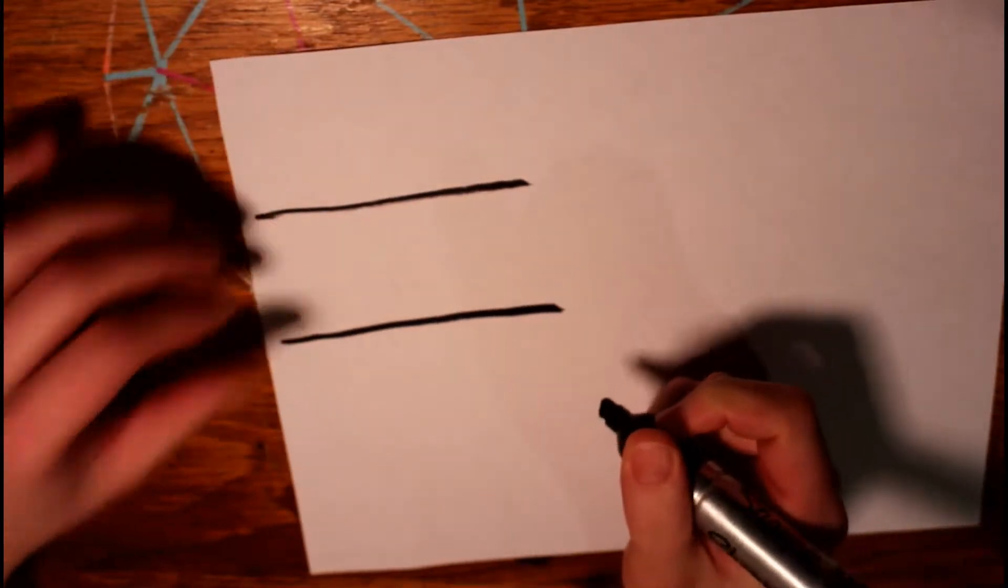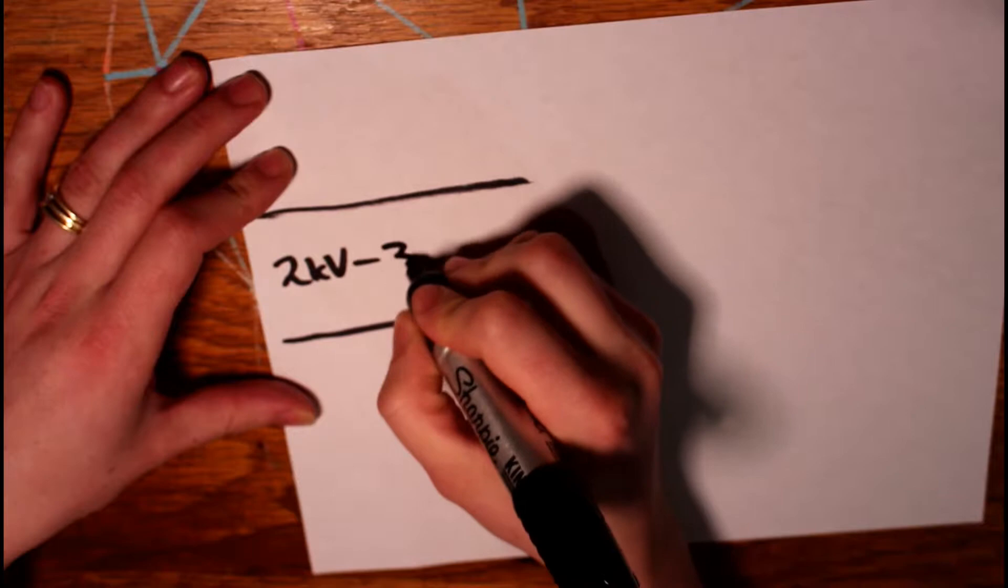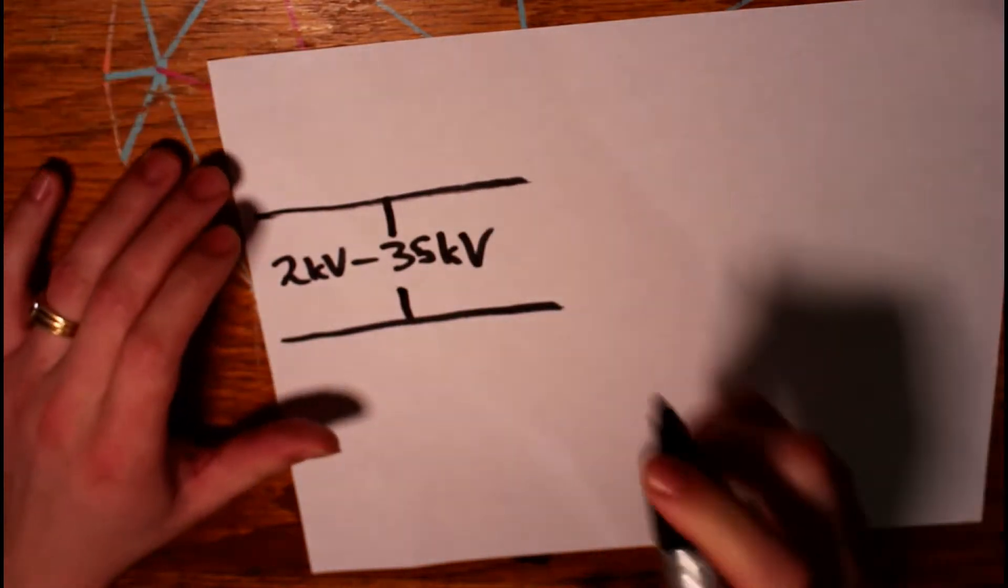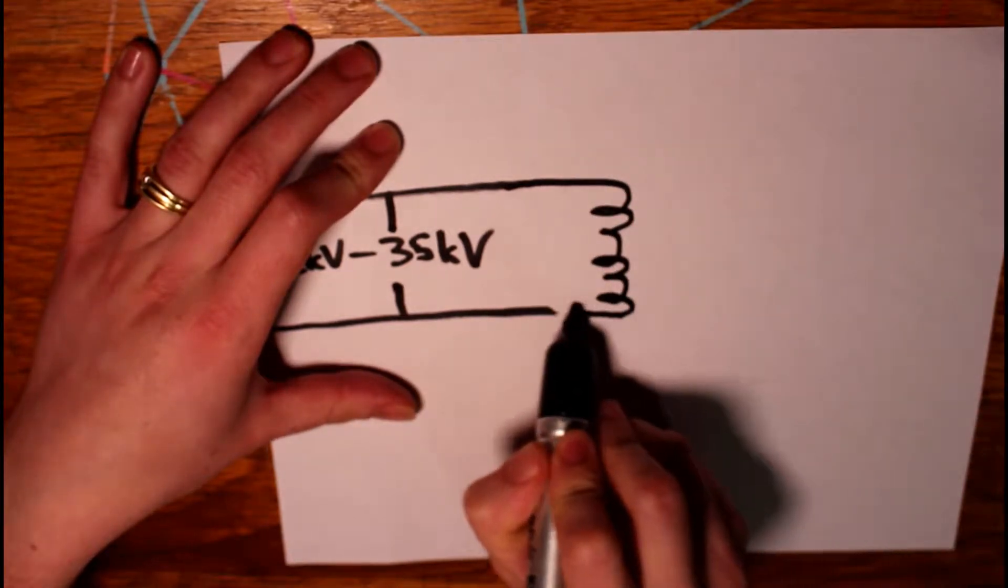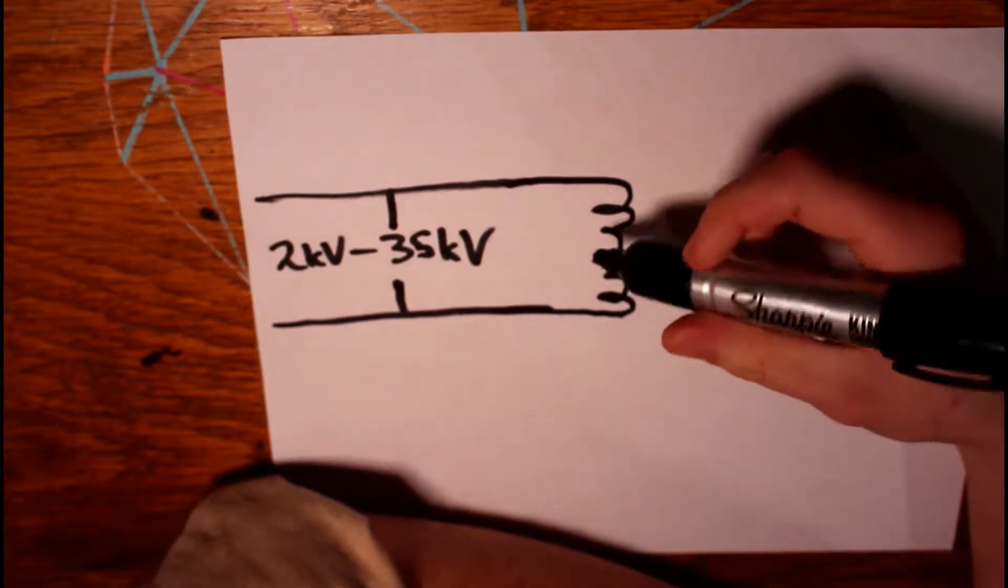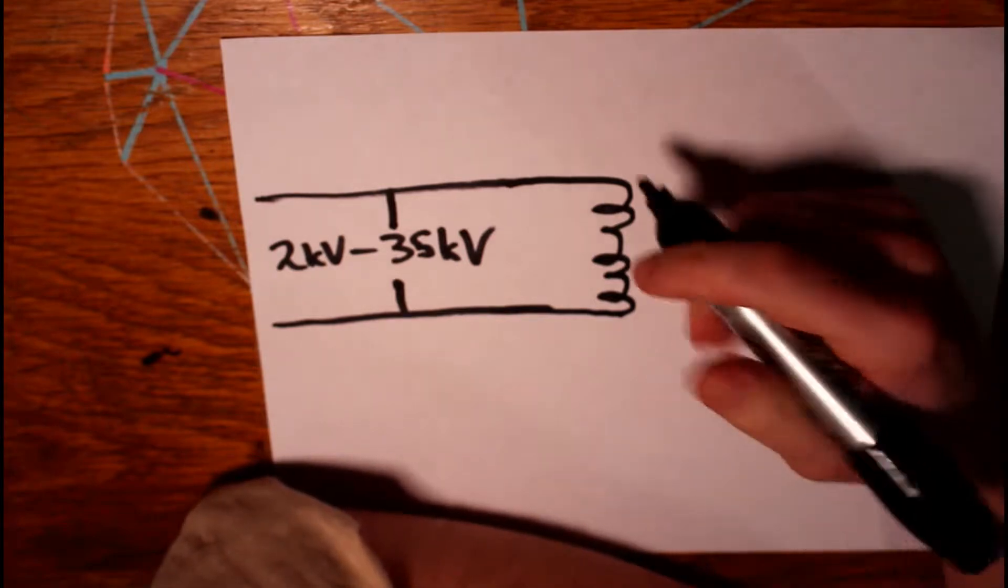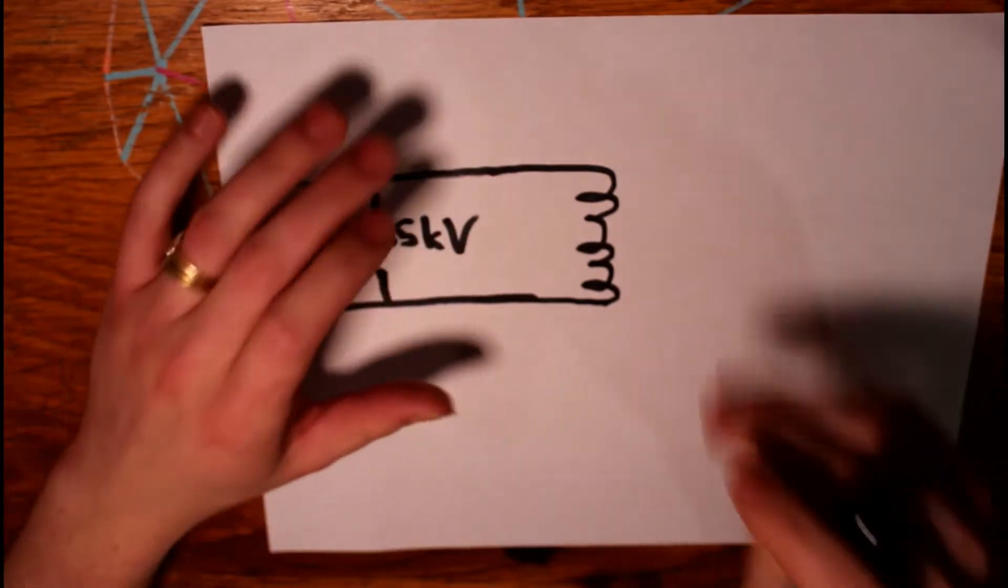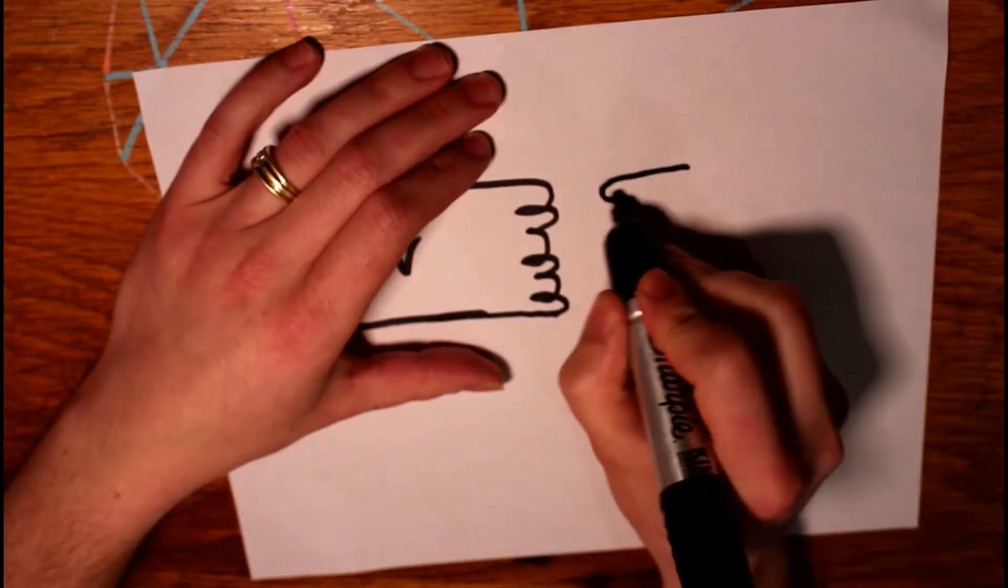To start off with, you've got the distribution lines running through your neighborhood, and for single phase, you'll have two lines with a phase difference, a phase voltage between them of 2,000 volts to 35,000 volts. That just depends on the distribution technology where you live. That then goes into the primary side of a transformer. These will be the cylindrical looking things on the tops of the power poles, or you might have a boxy looking one that's mounted to a concrete slab on the ground. This transformer has a secondary, which actually feeds your house.